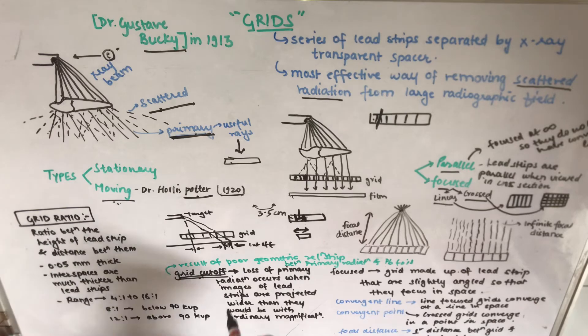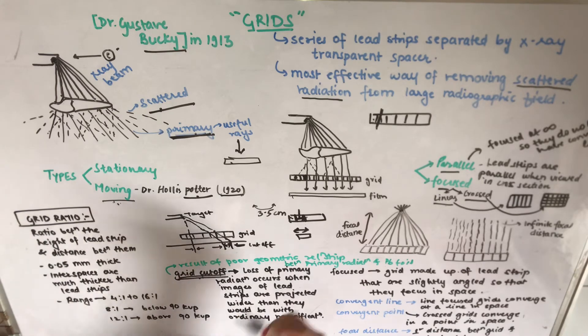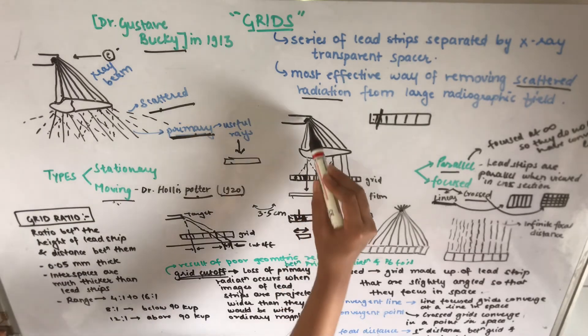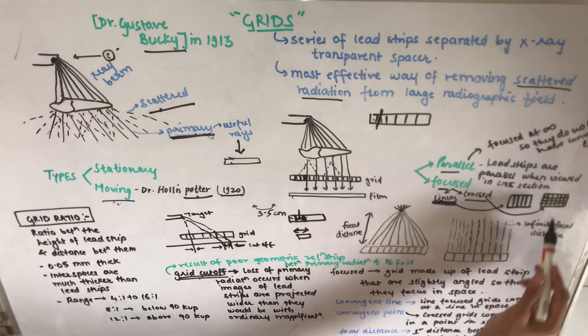The linear type of grid can only be used effectively with very small x-ray fields or when the target-to-grid distance is long. The cross grid is made up of two superimposed linear grids at right angles to each other with the same focusing distance. The disadvantage of the cross grid is that it cannot be used with oblique techniques that require angulation of the x-ray tube.